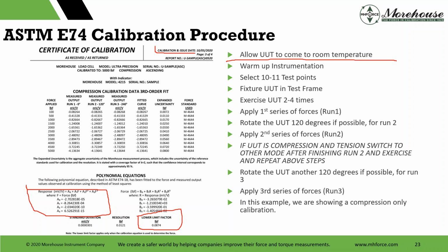So it gets put on a schedule, and then it gets plucked. And when it gets plucked, we say, hey, we're going to warm up the instrument. Typically 20 to 30 minutes. So we're going to turn it on, warm it up, let everything saturate, let it heat up, let the load cell heat up to the instrument. We're going to warm it up, 20 to 30 minutes.